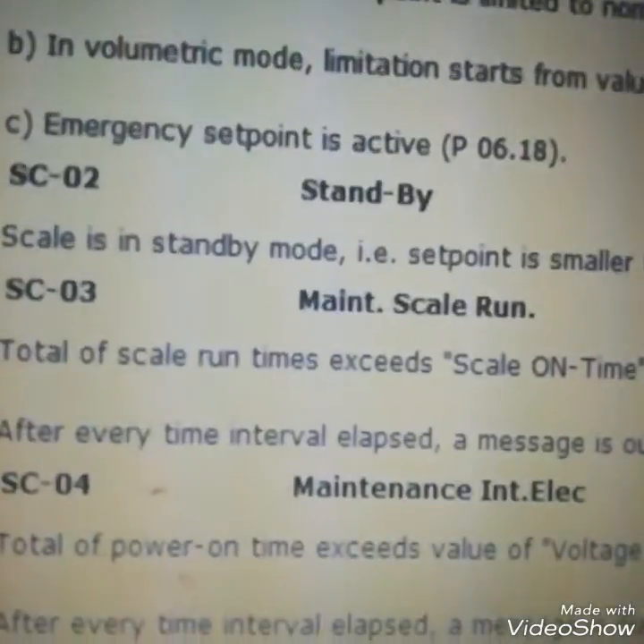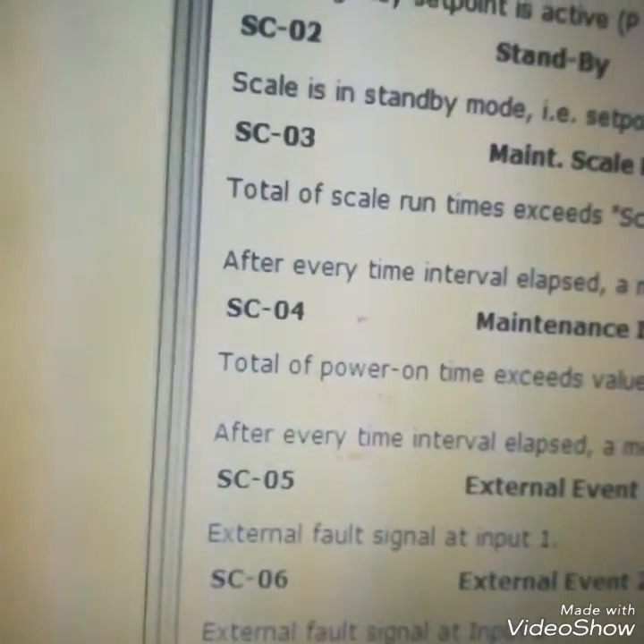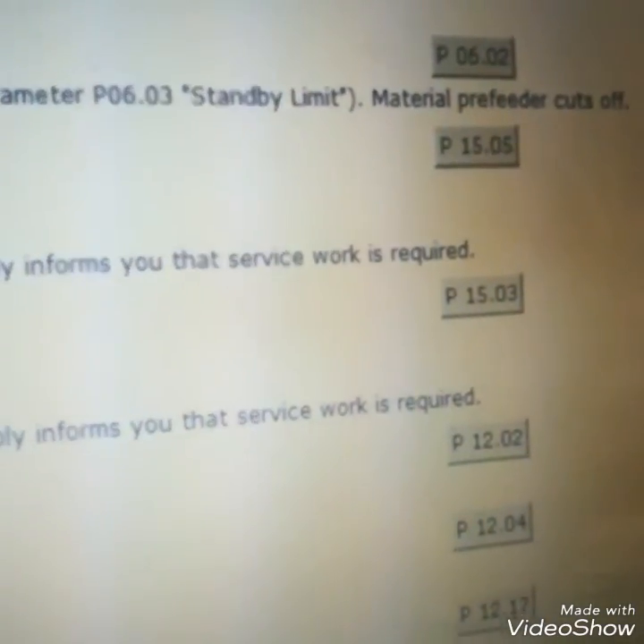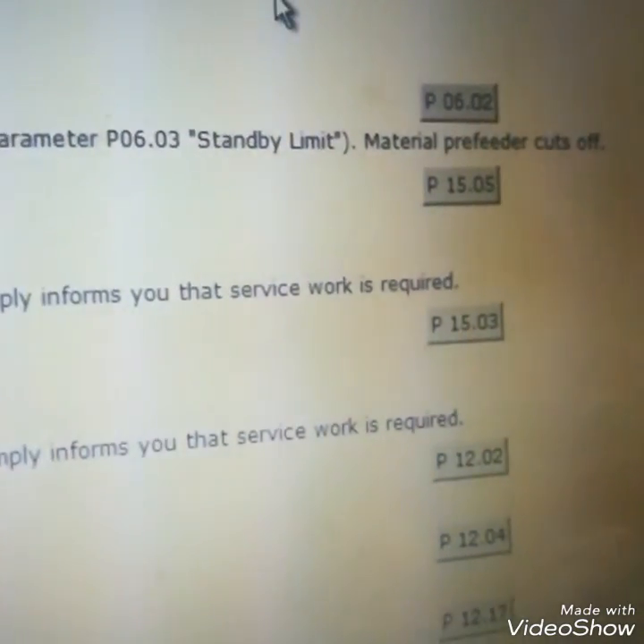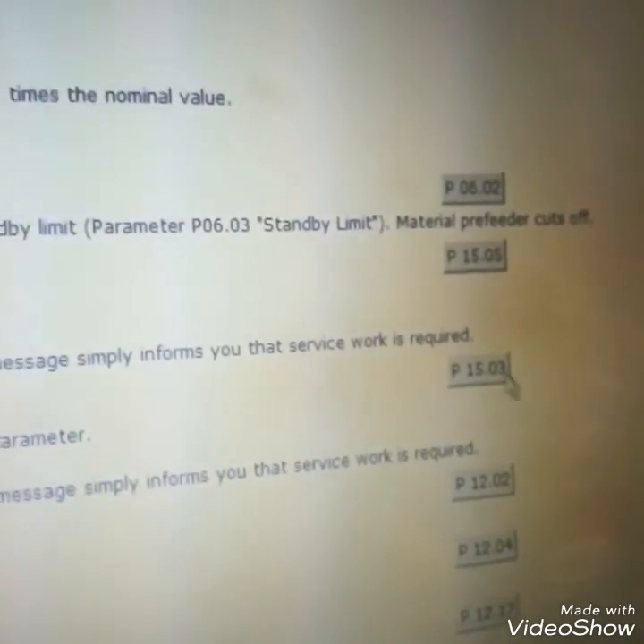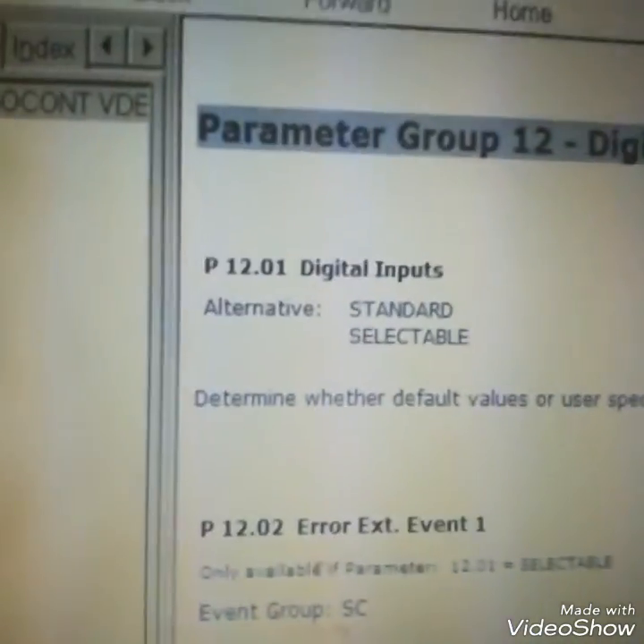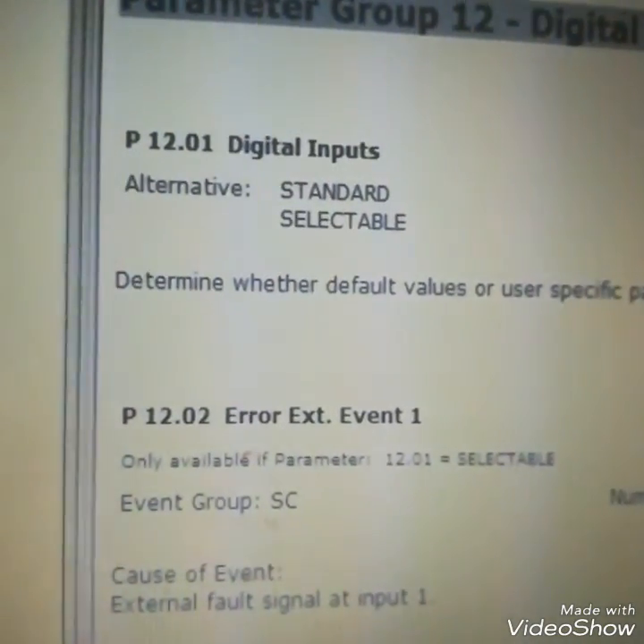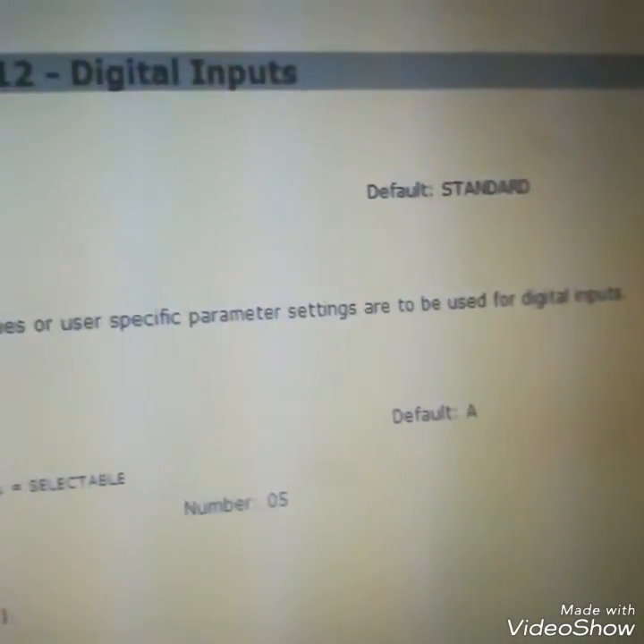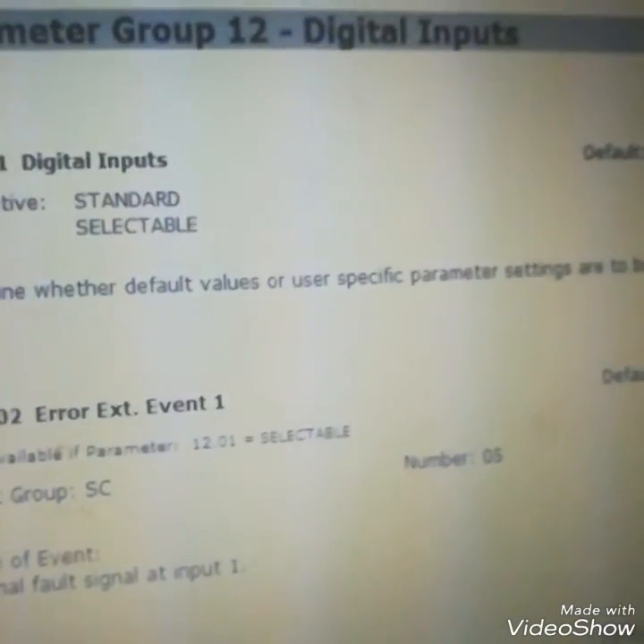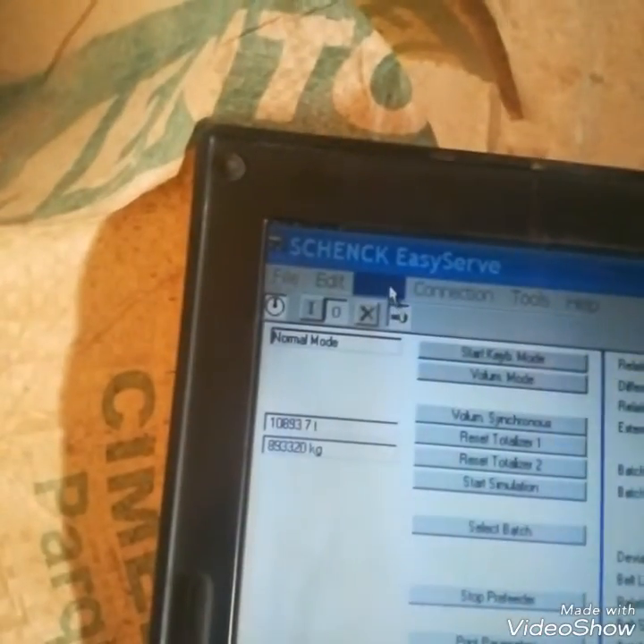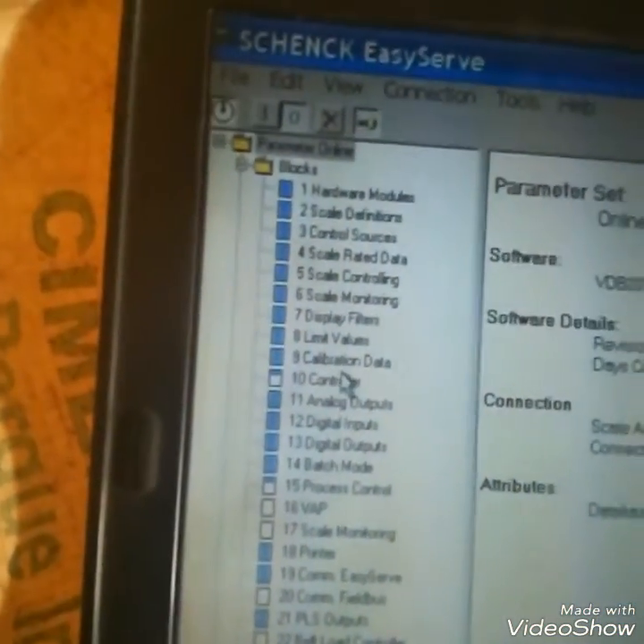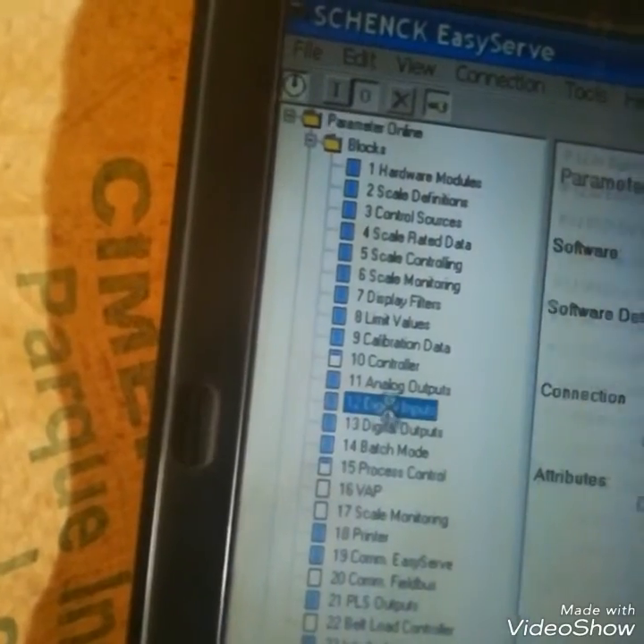Here I clicked it. You can see it's showing HTML help. It's showing the fault. It's showing from which parameter this fault is configured. I can go to that parameter and check it here. You can see I just press this, it will show its detail, from where this fault is generated. So it's very easy to go to the root cause and to the parameters, so we can trace the fault from where it is configured and from where it is generating. It's very easy.